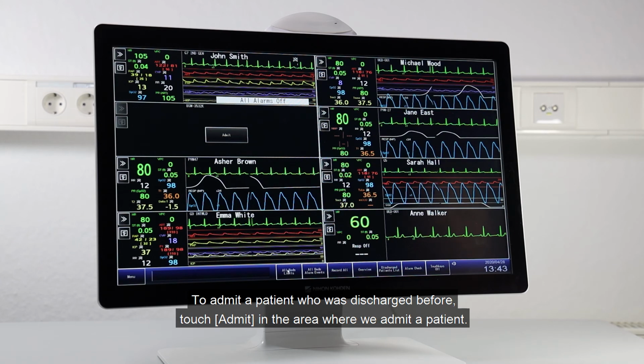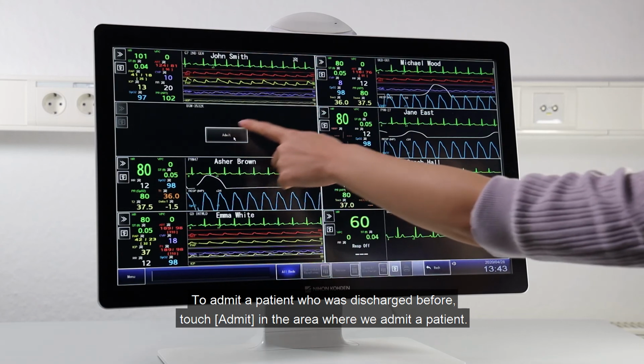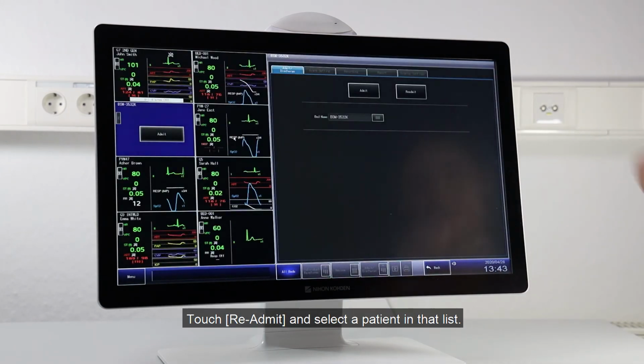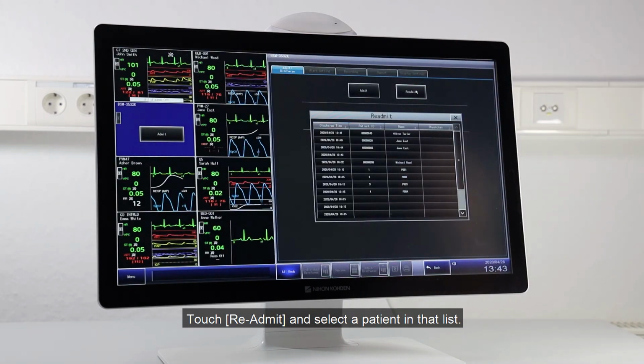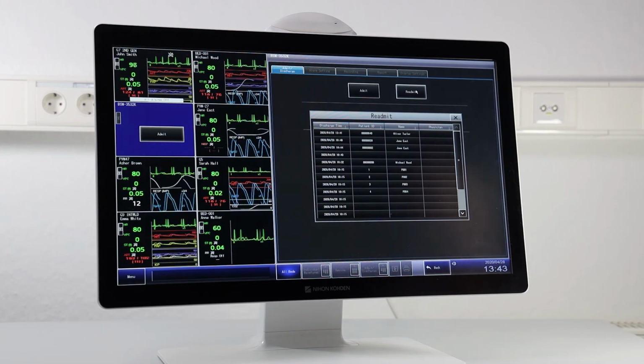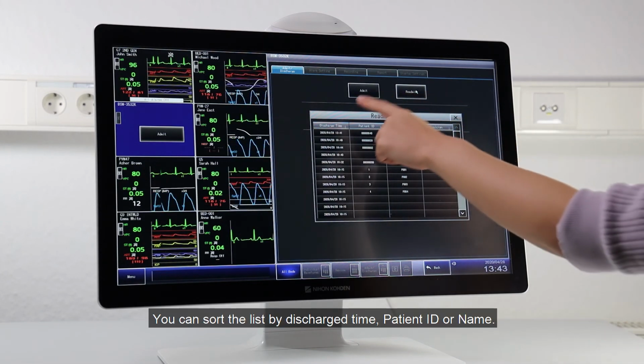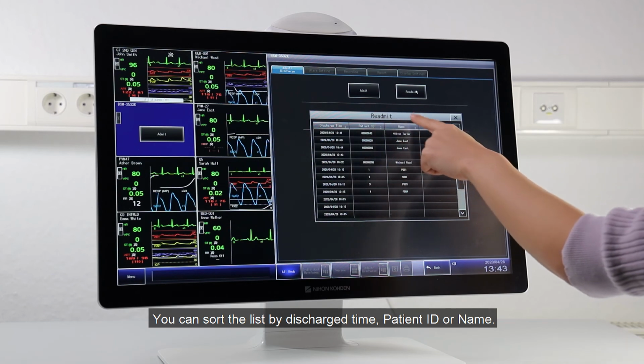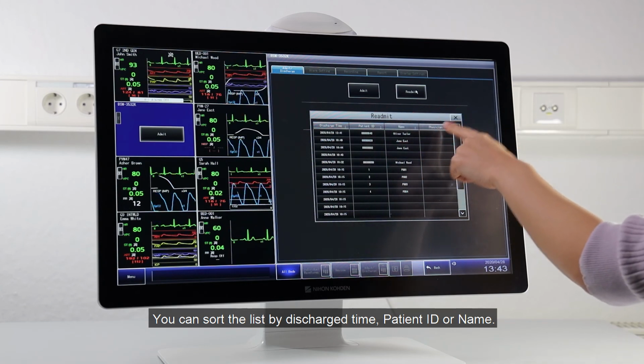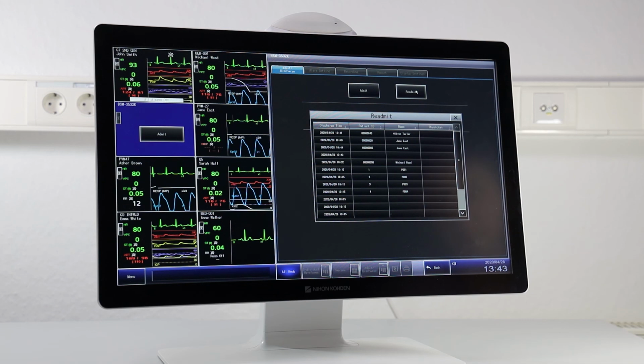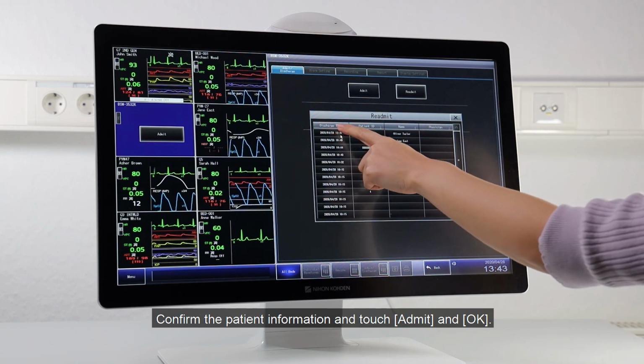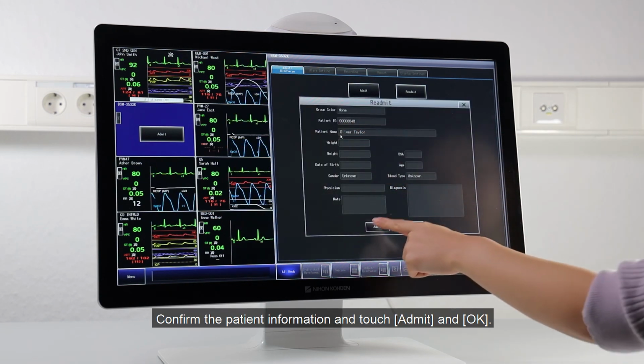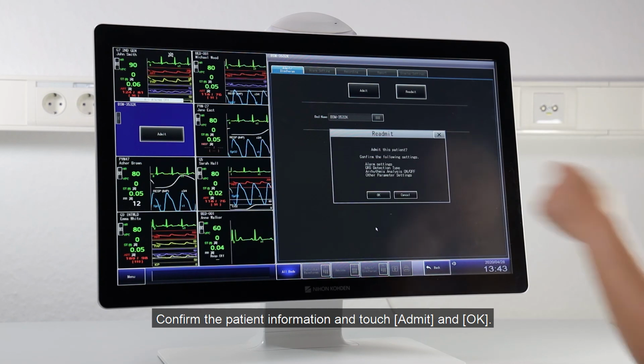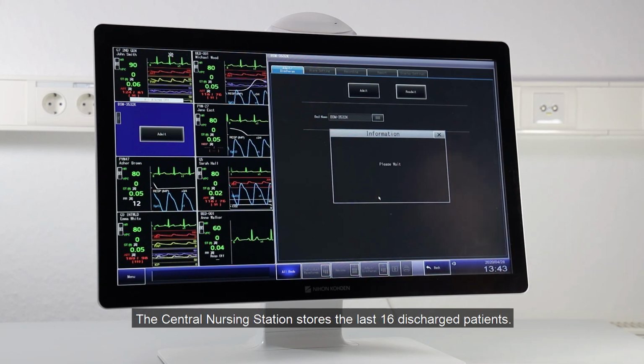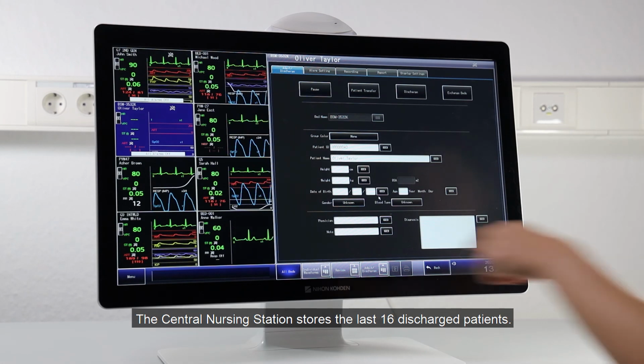To admit a patient who was discharged before, touch Admit in the area where we admit a patient. Touch Readmit and select a patient in that list. We can sort the list by discharge time, patient ID, or name. Confirm the patient information and touch Admit and OK. The central nursing station stores the last 16 discharged patients.